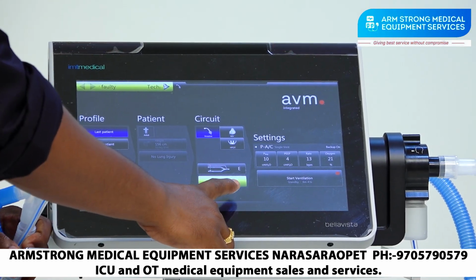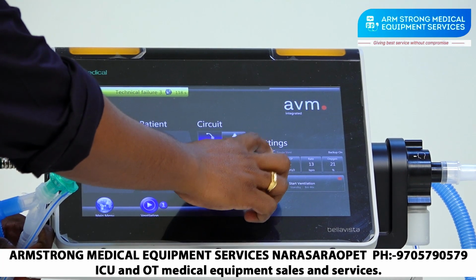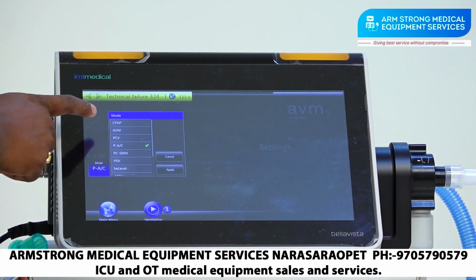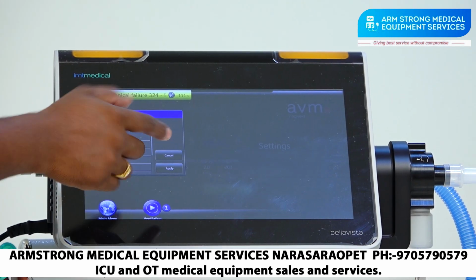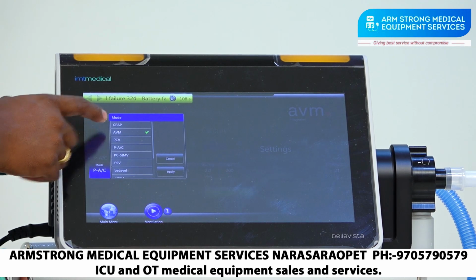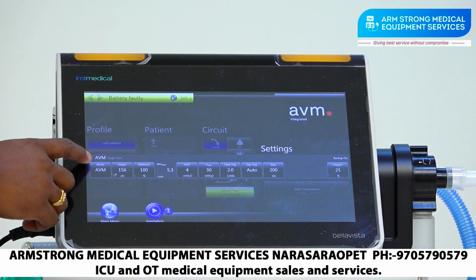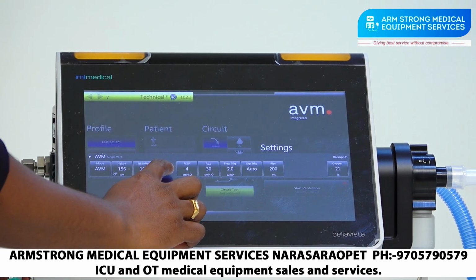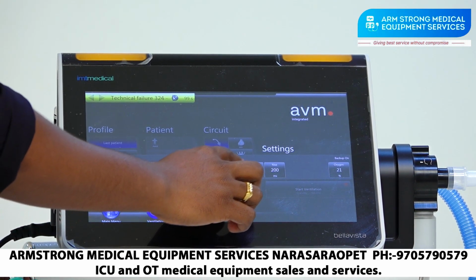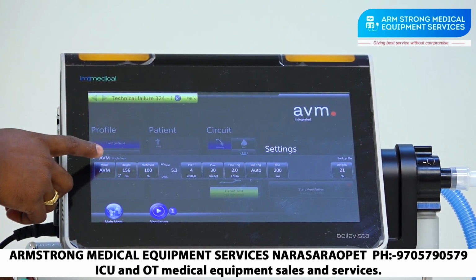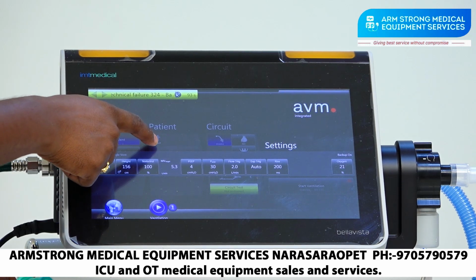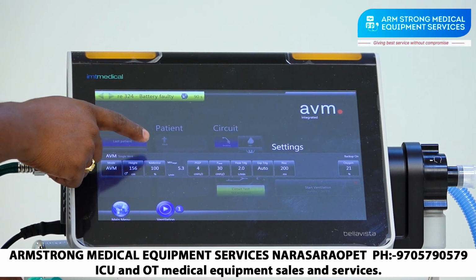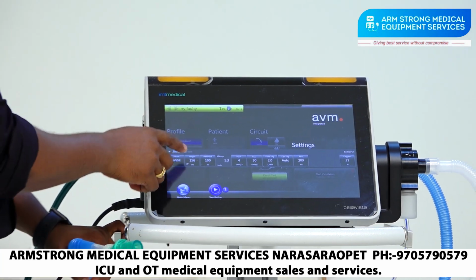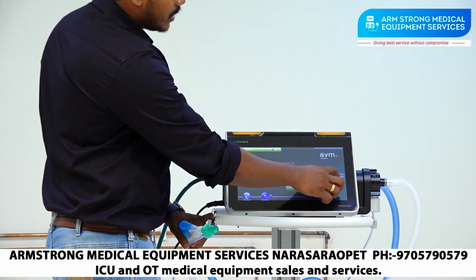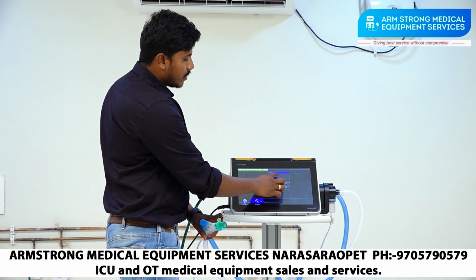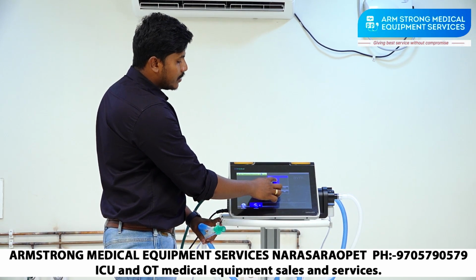So after the circuit test is performed, just see here, these are the ventilation modes. I will explain this ventilator's particular feature, AVM mode only. I will just apply that one only. So here AVM mode. See, this is the minute volume target, P limit. So automatically all these things came. Why? Because we have already selected the adult mode and patient category and patient IBW also. So depending on that, these all came automatically. Just we can select the oxygen concentration, so depending on patient saturation, we can choose this.